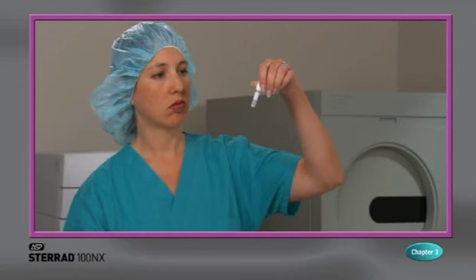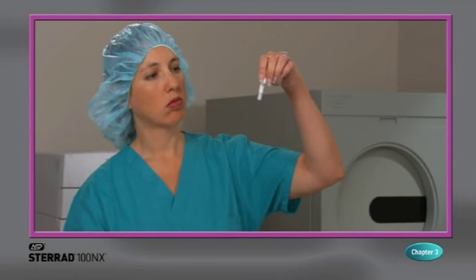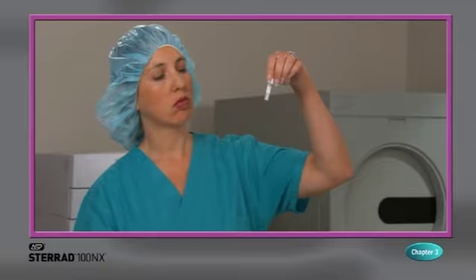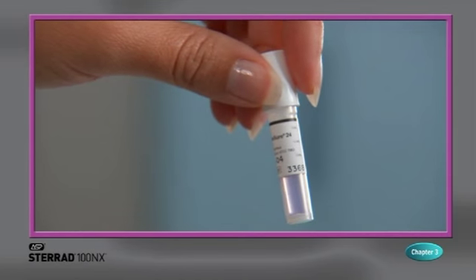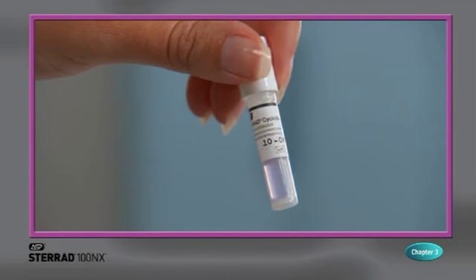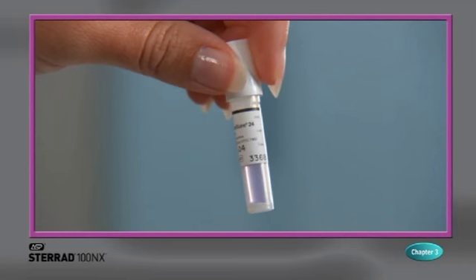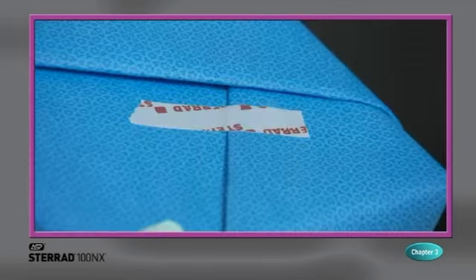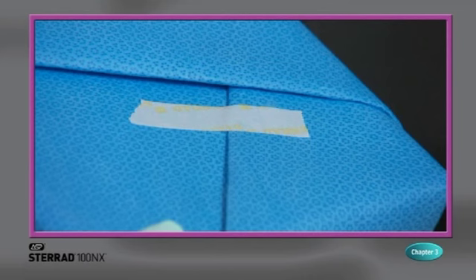Before processing a Sterrad CycleSure 24 biological indicator, or BI, make sure it is intact. Check the lot number and label it according to your facility's policy and procedures for biologicals. The Sterrad SealSure chemical indicator tape and the Sterrad chemical indicator strips change from red to golden yellow when exposed to hydrogen peroxide. Yellow indicates processed and red indicates unprocessed.